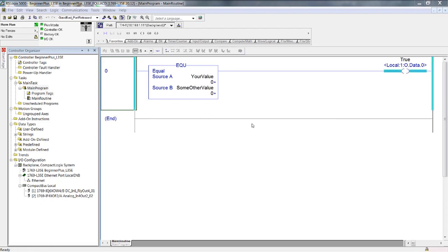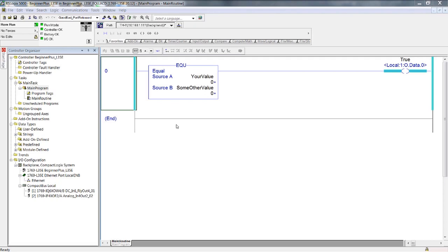Now we're online; I put it in the online run mode using an L35E CompactLogix processor simply because it's much faster for upload, download, and online edits — just to shorten the video time. The answer to the very first question is yes, the rung is true. Had you saved your project, downloaded, and gone online in run mode: if A equals B, then B equals A — of course it is. I had you edit your logic to add another equal instruction and reverse the order of source A and source B, just to show that the rung is still true.